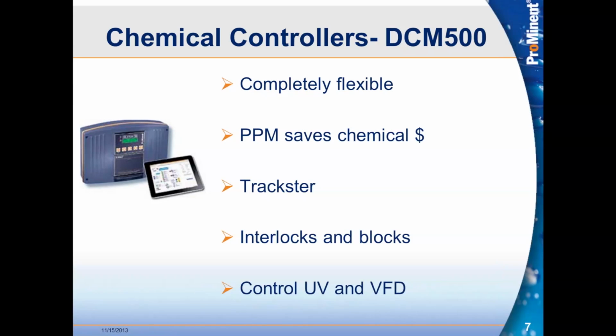One of the other attractive things for me with the flexibility of the DCM 500 is what we call interlocks and blocks. Traditionally, with other controller manufacturers, in order to get an interlock going, we have to hardwire something from device to device. What we can do with the DCM 500 is take in wires that give us a signal off of an outboard device, let's say a VFD, a filter controller, or an autofill system, and we can digitally provide interlocks and blocks.